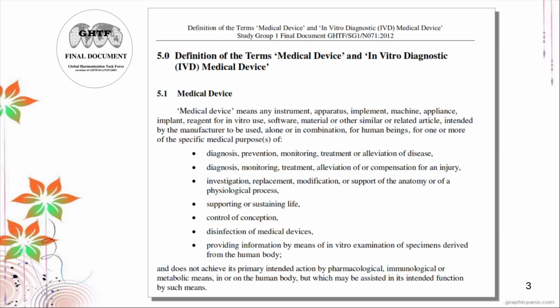So let's say, for example, is a lotion considered a medical device or does it fall under drugs? We can say that since a lotion is supposed to be absorbed, even if it's a topical lotion, you have some sort of absorption there by the skin. So it falls under an action that has a pharmacological, immunological, or metabolic means. So it's not a medical device, but rather it falls under the definition of a drug.